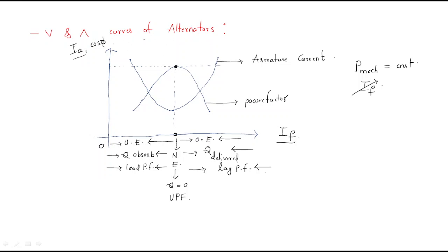To summarize: when the alternator is under-excited, reactive power is absorbed and it acts at leading power factor. When over-excited, reactive power is delivered and it acts at lagging power factor.